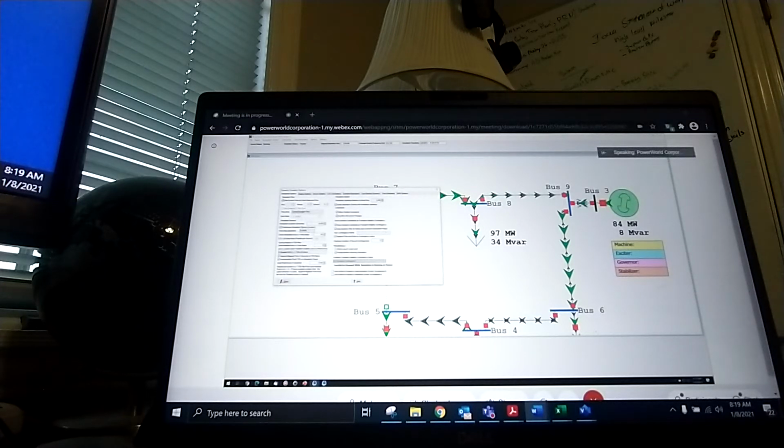Check simulation every n time steps. So I guess this would be checking for commands coming from the various clients. And then we've got, if you're sending out C37.118 data or PMU data, this is the decimation rate, or the rate in frames per second that is being sent out.